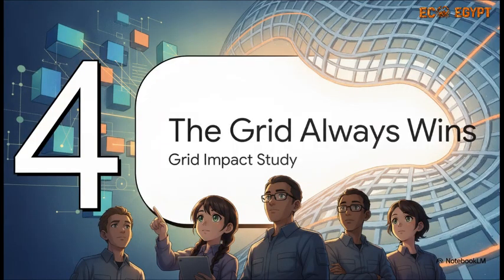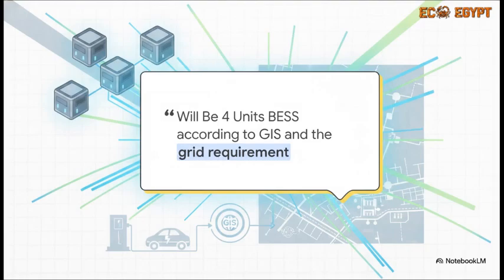And finally, section 4, the grid always wins. The grid impact study isn't just some minor footnote in utility-scale design, it is the ultimate authority. For this site, the utility looked at their 33 kilovolt network and realized they required 38 megavolt amperes of reactive power just to keep their voltage stable, along with 20 megawatts for peak shaving. Boom. That analysis alone entirely dictated the 45 MVA conversion system and the 20 megawatt-hour battery we chose. The local EV charging needs, the construction power, they just get to go along for the ride. The broader electrical grid dictates the final layout, period.